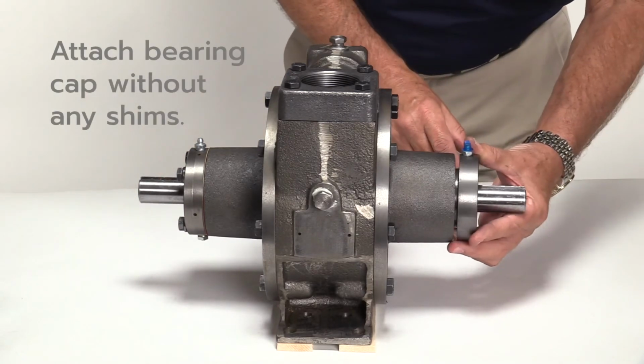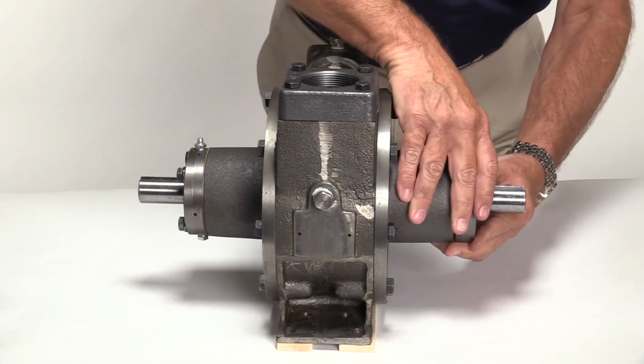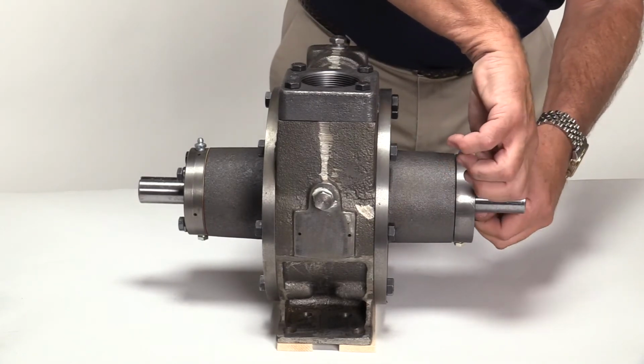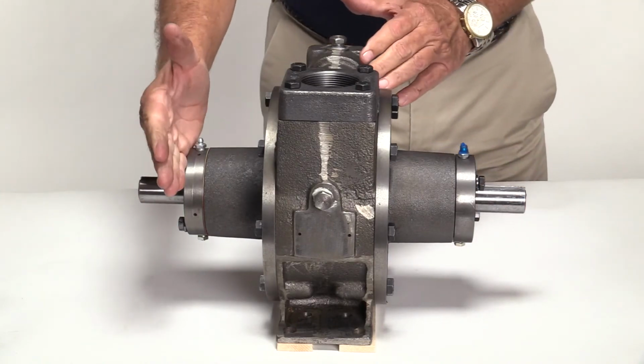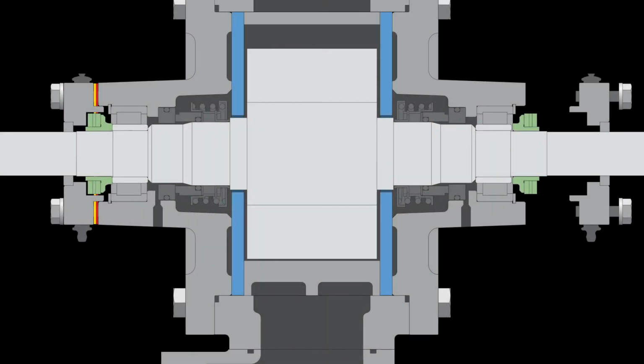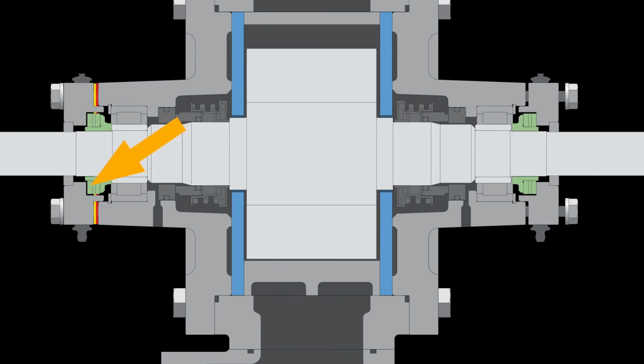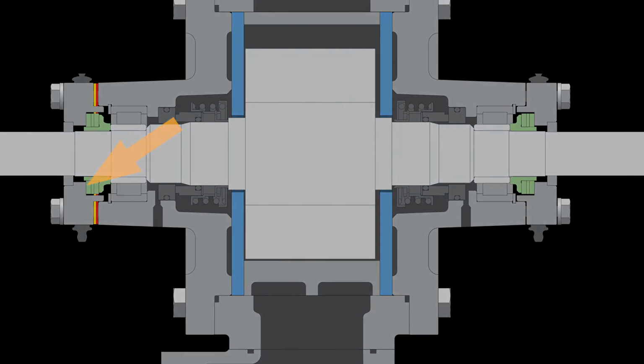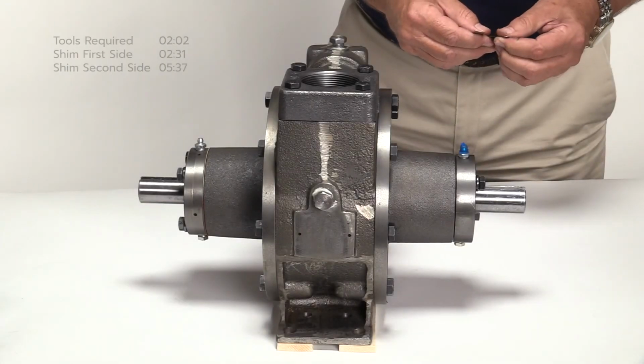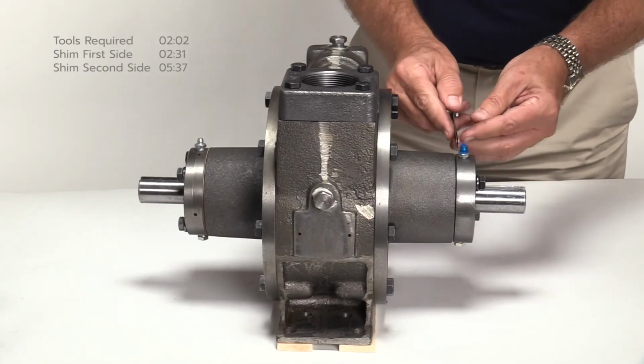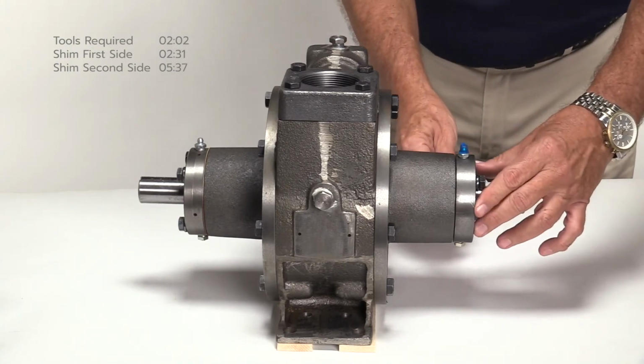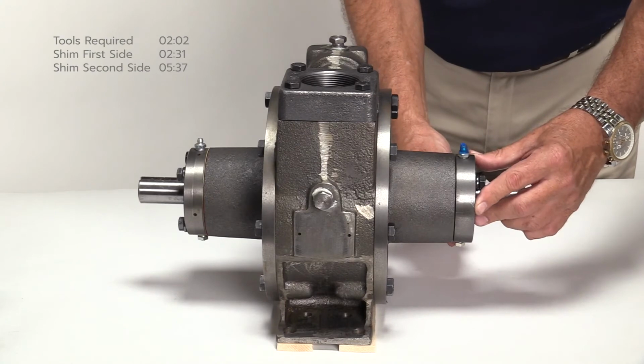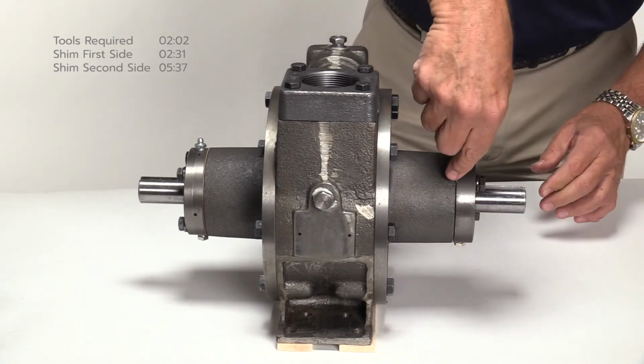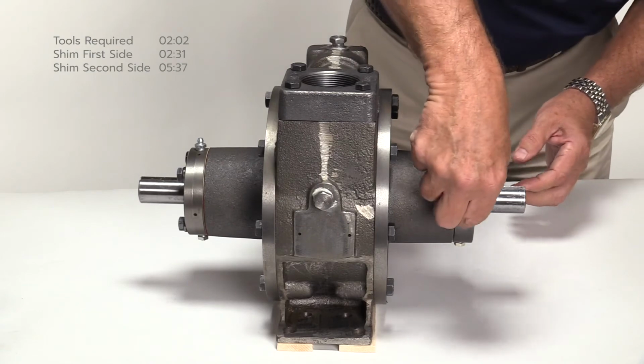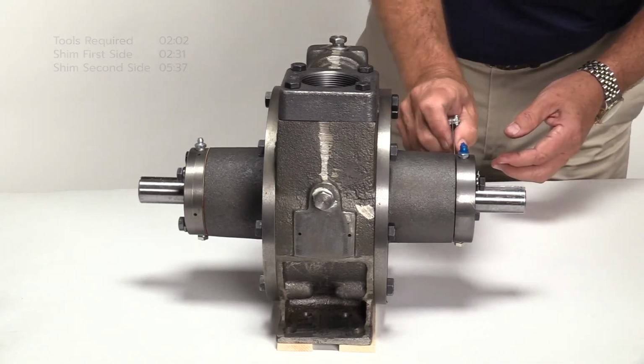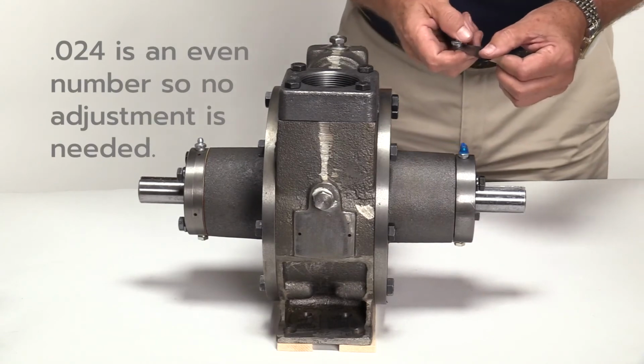Using 2 bolts, attach the bearing cap without any shims and tighten with fingers. This causes the rotor to force the thrust bearing against the bearing cap on the opposite side of the pump. Use the thickness gauge to measure the gap between the bearing cap and the pump head at multiple points as shown. This establishes a baseline for zero clearance. The gap should be the same at all points. If not, the bearing cap is not mounted flush with the pump head. The gap measures 24 thousandths. This is an even number, so no adjustment is needed.